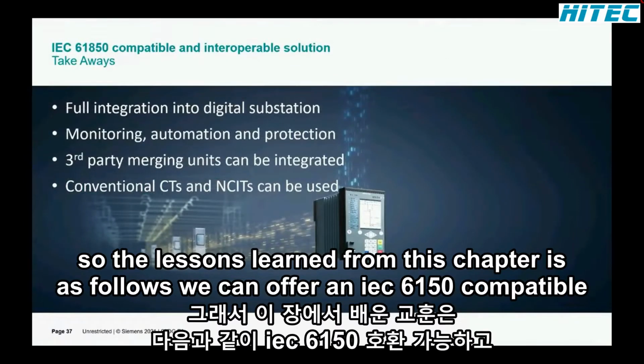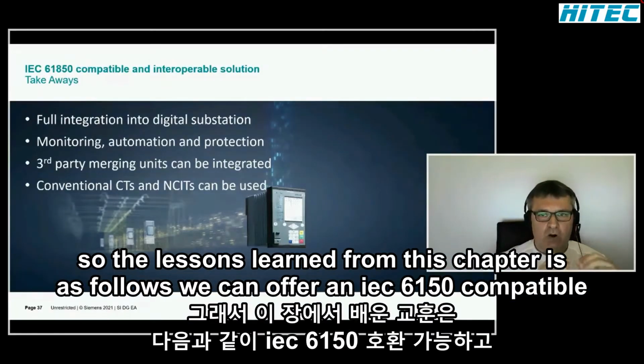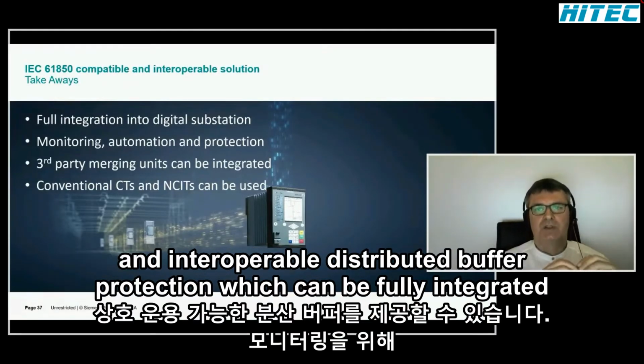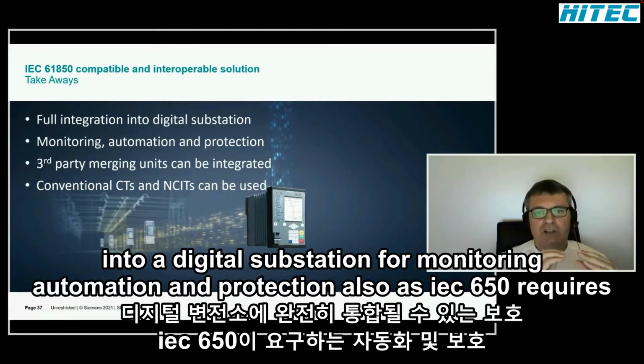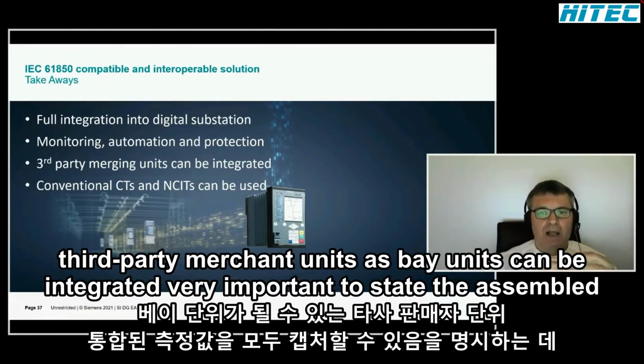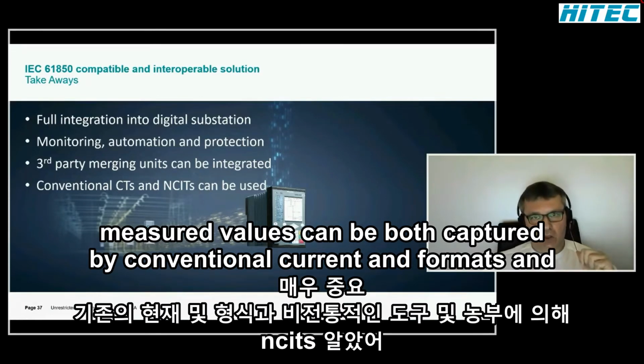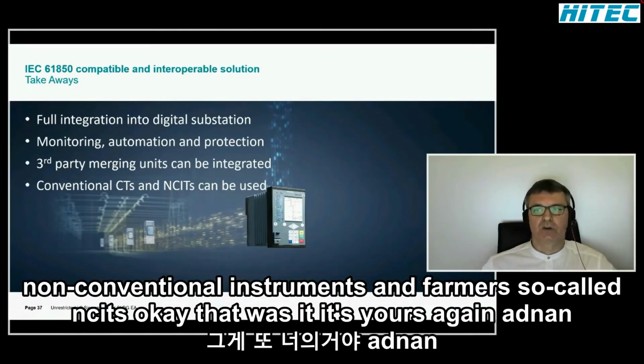So, the lessons learned from this chapter are as follows. We can offer an IEC 61850 compatible and interoperable distributed busbar protection, which can be fully integrated into a digital substation for monitoring, automation, and protection. Also, as IEC 61850 requires, third-party merging units as bay units can be integrated. Very important to state, the sampled measured values can be captured both by conventional current transformers and non-conventional instrument transformers, so-called NCITs. Okay, that was it.